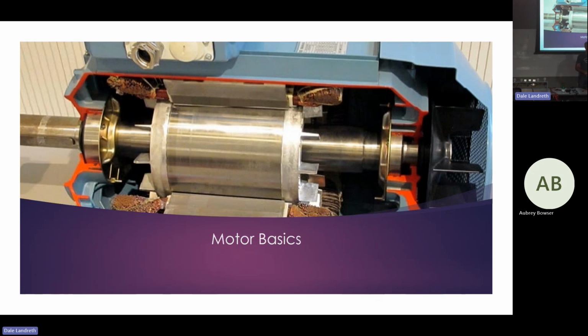And again, just understanding what you're doing and making sure that you isolate. It's just like checking a compressor or a motor. Compressor is probably the best example for me - condemning a compressor at the contactor. That's what that's like, because you didn't go right to the motor, you didn't go right to the motor leads. And I tell you, I've condemned a compressor from the contactor before. That will make you feel stupid.